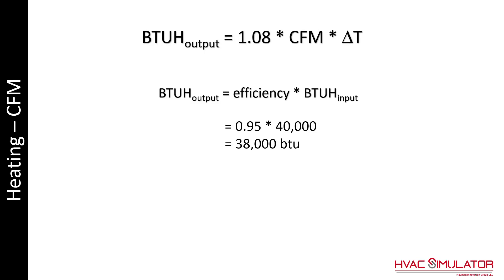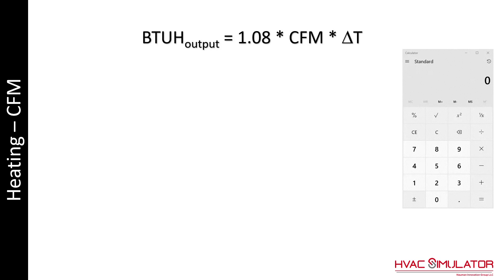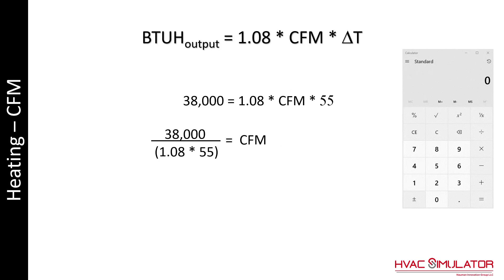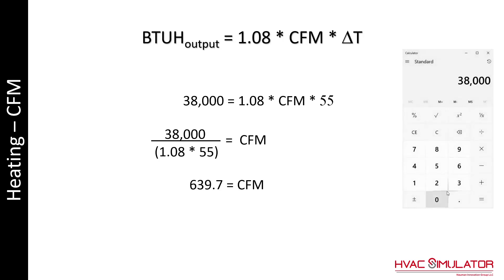Calculate the BTU output by multiplying the BTUs by the efficiency. 0.95 times 40,000 is 38,000 BTUs. Substitute into the sensible heat equation and solve, which gives 639.7. On the calculator: 38,000 divided by 1.08, then divided by 55.